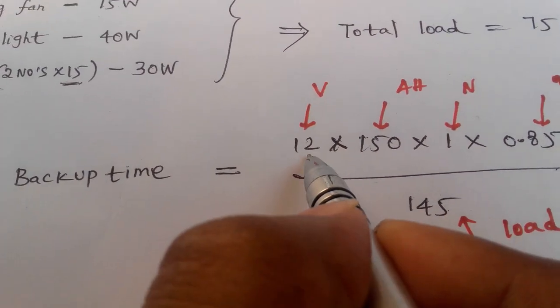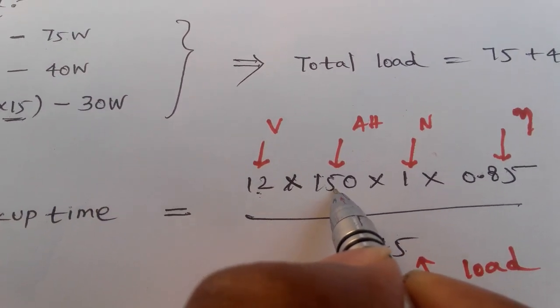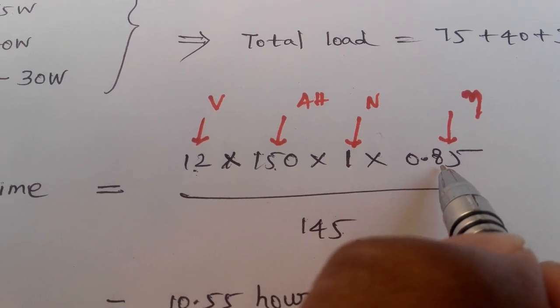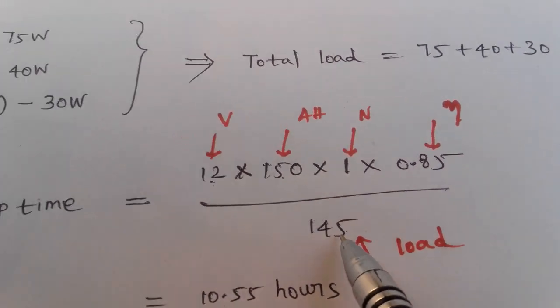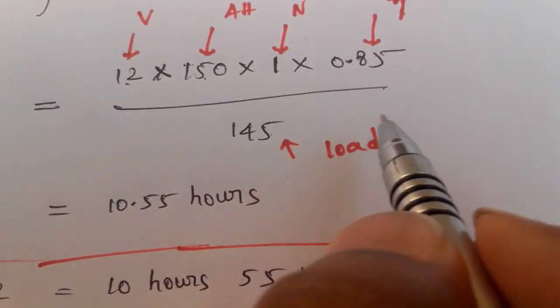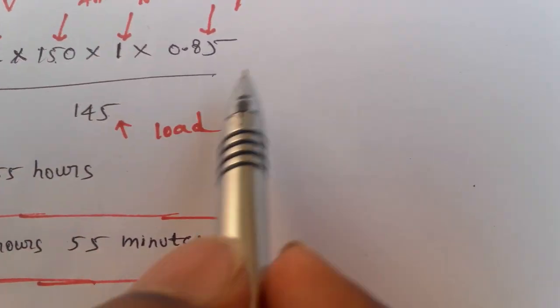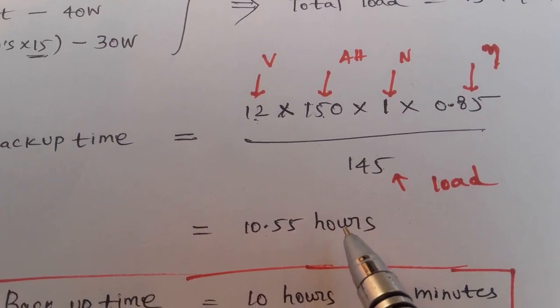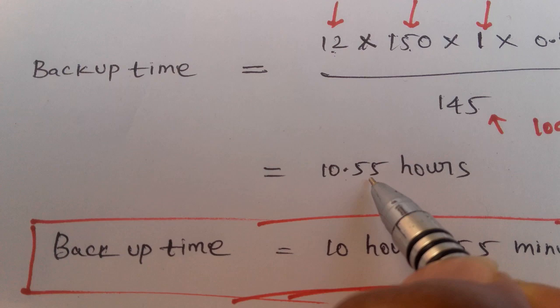Backup time equals battery voltage 12V times ampere hour 150Ah times N which is 1, times efficiency 0.85, divided by the load 145W. If you simplify this, it equals 10.55 hours, that is 10 hours and 55 minutes.